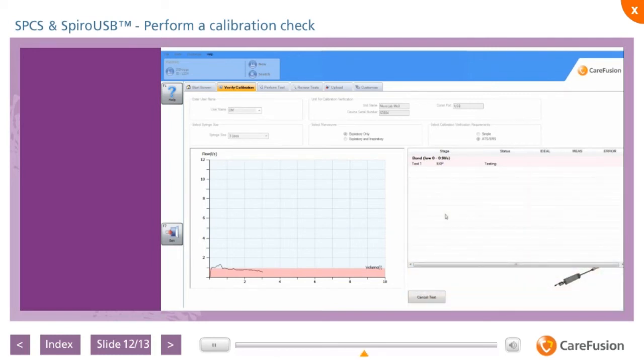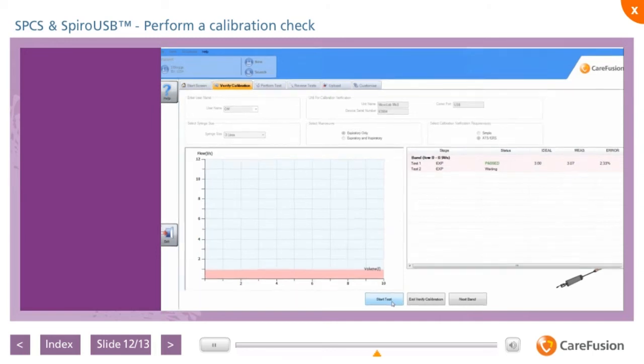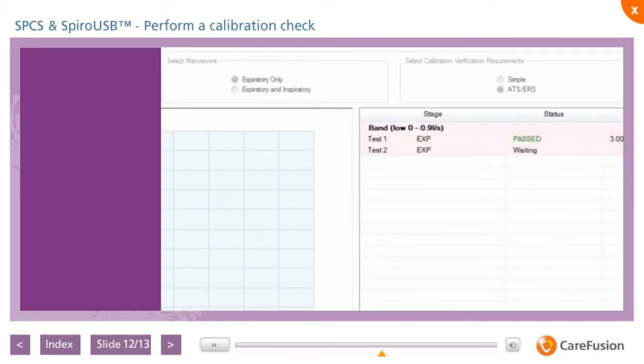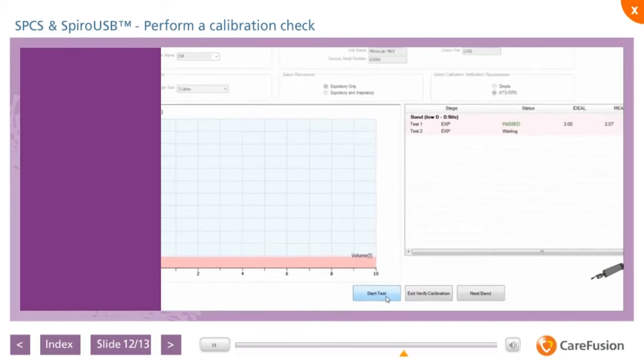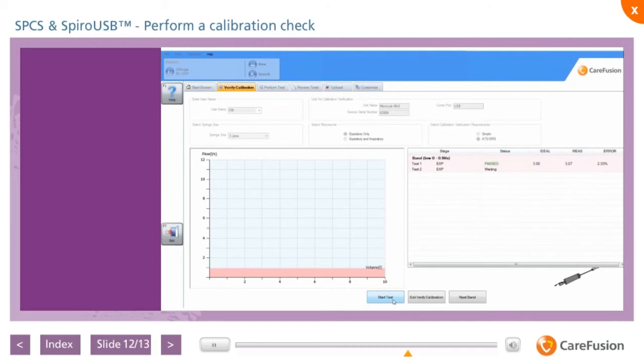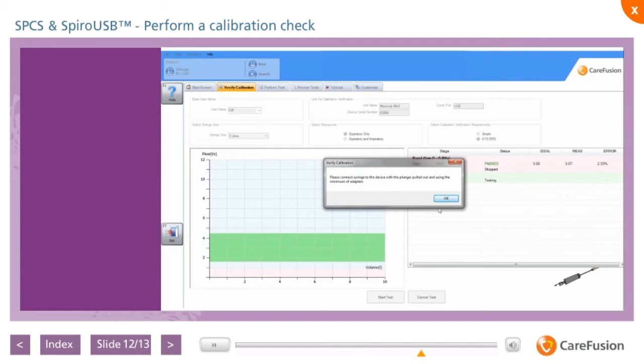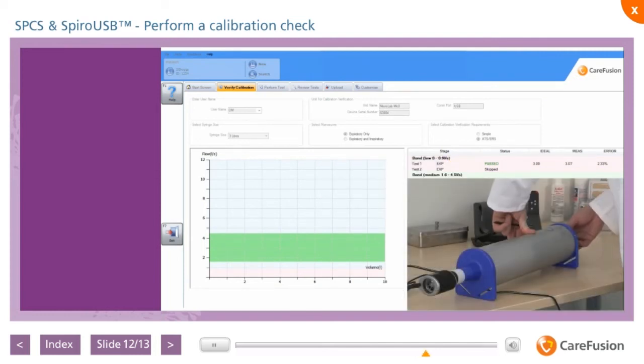When emptying and filling the syringe, the maneuver should be performed at a smooth, sustained speed, taking care to avoid slowing down or stopping during the maneuver. For this demo, expiratory verification is chosen, and therefore the airflow is recorded when emptying the syringe. If the maneuver has a pass status, then you can either repeat the maneuver in the current band by selecting Start Test, or choose to move to the next band. If you choose to move to the next band, then the result screen will show the skipped message to show you've moved without continuing to perform 3 maneuvers in a given flow rate.